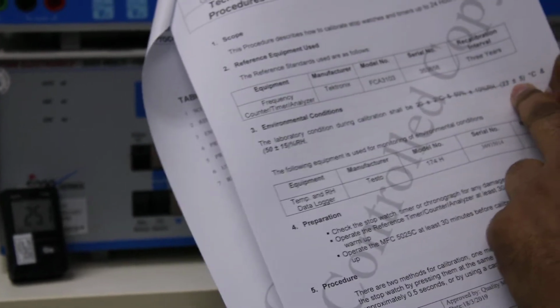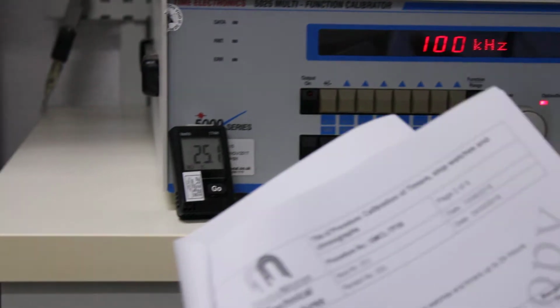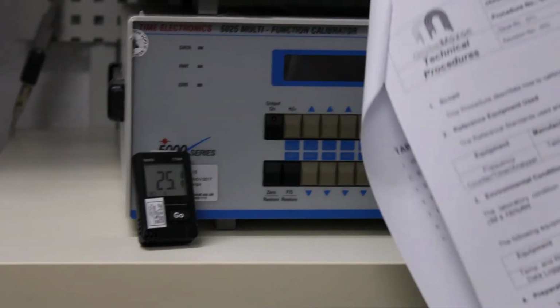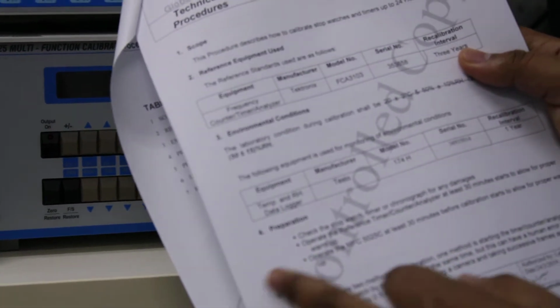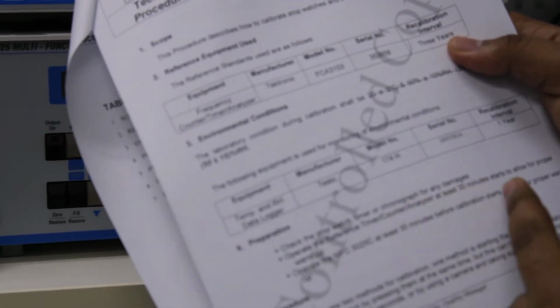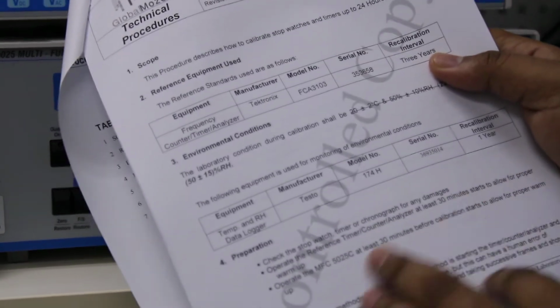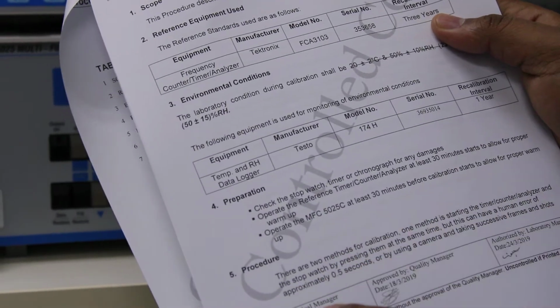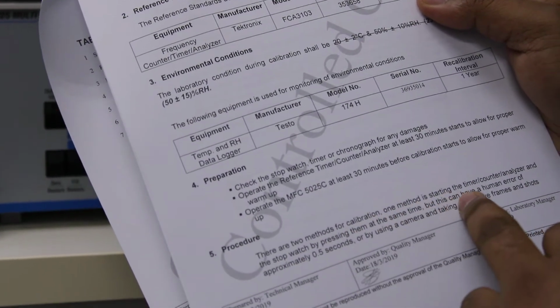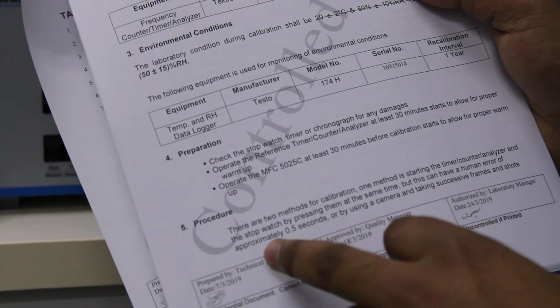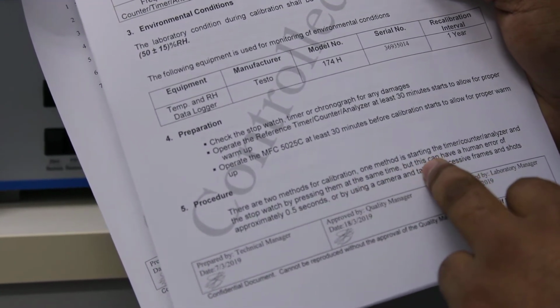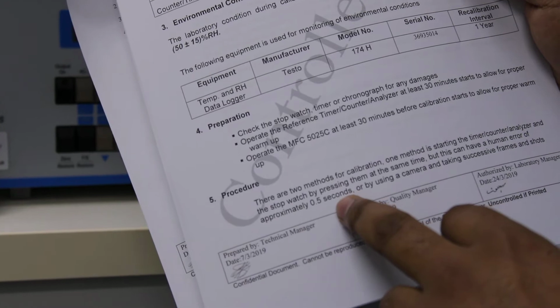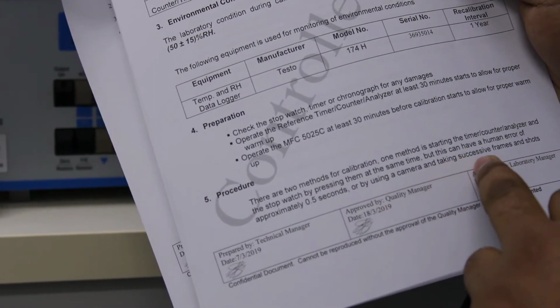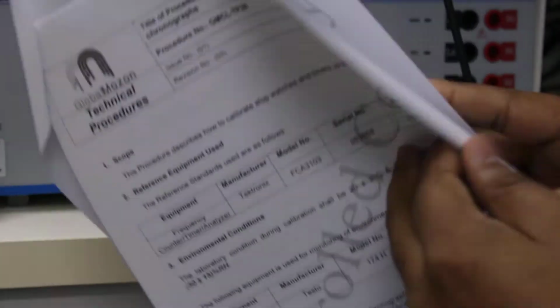Environmental condition is 20 plus or minus 2 and 50 plus or minus 15 RH. Now it is 25 plus or minus 1.1, and we keep a data log regarding the temperature. For preparation, we have checked the stopwatch for no damage, and we started it one hour before, so proper stabilization time has been given. For the procedure, there are two methods. One method is setting the timer counter analyzer and pressing the stopwatch at the same time. This can have a human error of approximately 0.5 seconds, unless using a camera and taking successive frame shots. So we are using the human method.